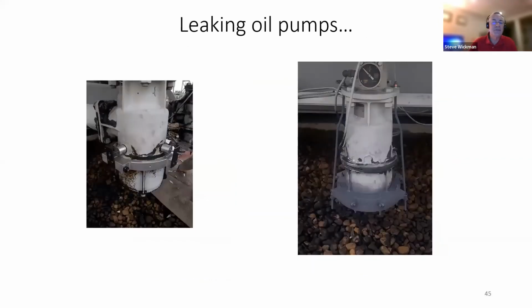Pumps, your larger transformer, your forced oil cooled transformers with pumps, as opposed to taking the pumps off, getting them refurbished and rebuilt, we can do a clamp around some of the flanges on those that will develop leaks. And here's two little repairs that we did. I know for a fact, because I personally took these photographs, that this transformer was in service when these repairs were made. They probably turned the pumps off one at a time for the work to be done. And upon completion and everything curing up, you can see in this one here that the flow gauge is in the pump on oil flowing position.